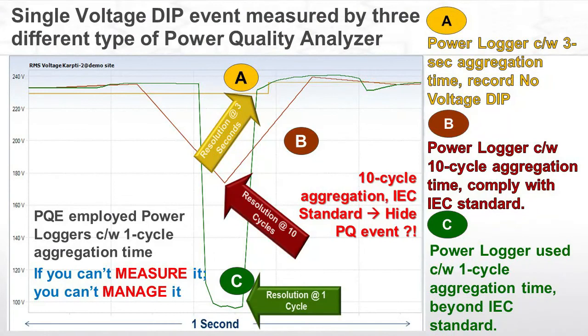To demonstrate the impact of aggregation time on voltage dip measurement, we performed tests using three different types of power quality analyzers measuring the same single voltage dip event. Power quality analyzer A has a 3-second aggregation time. Power quality analyzer B has a 10-cycle aggregation time, which is 100% compliant with IEC 61000-4-30 Class A requirements. Power quality analyzer C has a 1-cycle aggregation time, also 100% compliant with IEC 61000-4-30 Class A and beyond that standard.